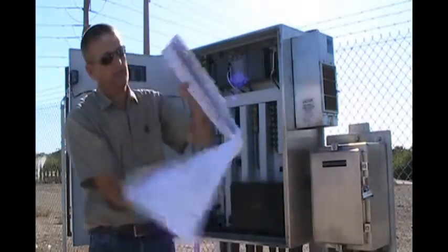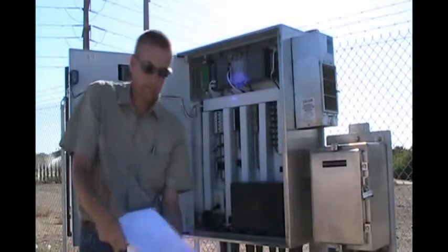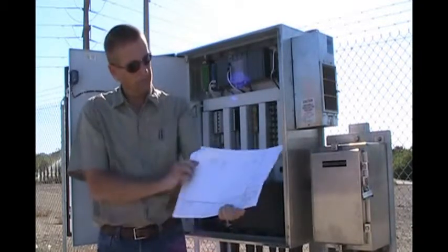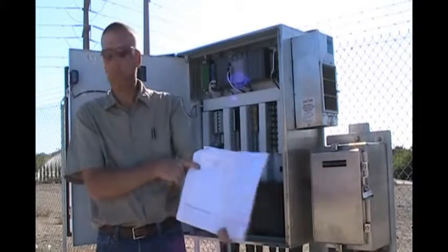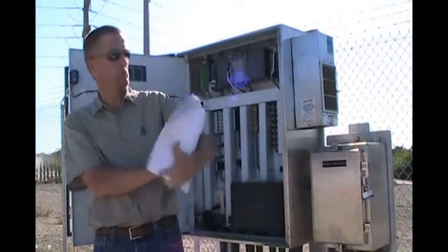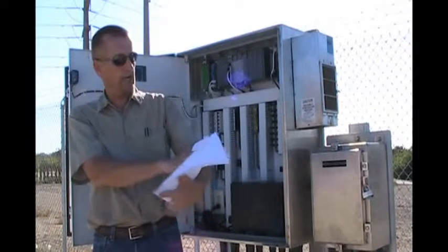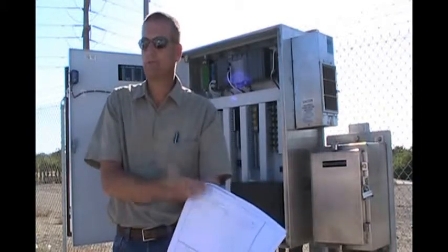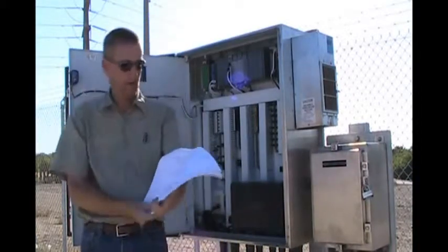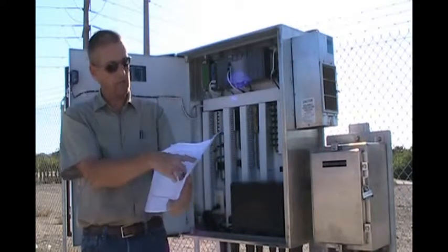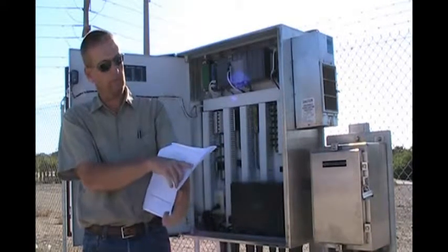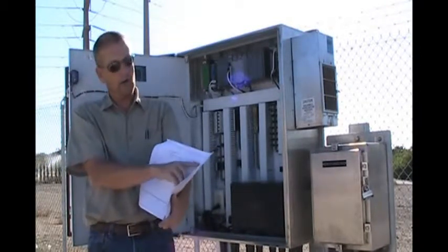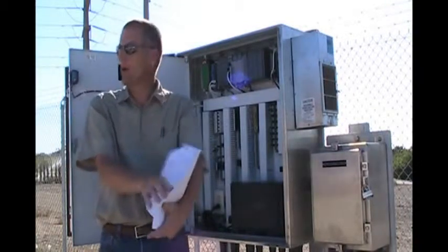Then we go to our loop drawings, same as before. We have on the left side the field devices, on the right is to the RTU, and we give a description of the level transmitter. This one happens to be 2001. It goes through a direct terminal enclosure, which includes the surge suppressor, or the diodes, and then from there it goes into the terminal blocks in the cabinet. And I give you the terminal block, the fuse size is in there, and then it gives you the input of the card, the rack slot and point in that card.